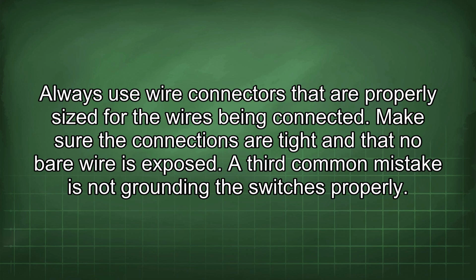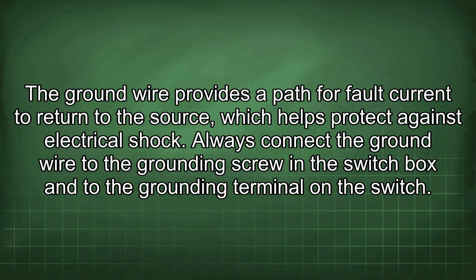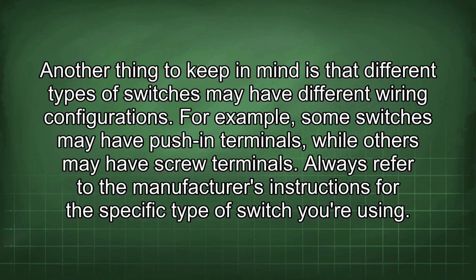A third common mistake is not grounding the switches properly. The ground wire provides a path for fault current to return to the source, which helps protect against electrical shock. Always connect the ground wire to the grounding screw in the switch box and to the grounding terminal on the switch.